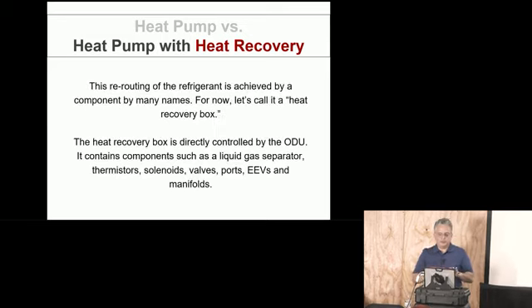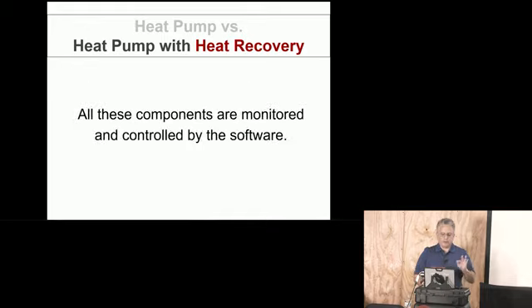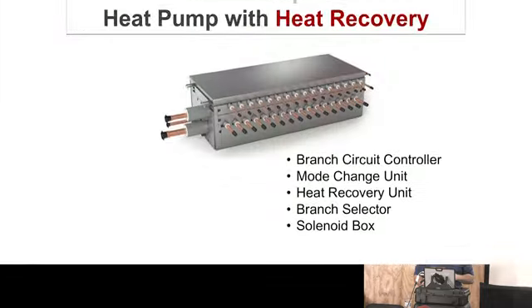This rerouting of the refrigerant is achieved by a component by many names. For now, we'll just call it heat recovery box. We'll go over the different names in a later section. The heat recovery box is directly controlled by the outdoor unit. So if you have a heat recovery box, it's an extension of the outdoor unit. It contains components such as a liquid gas separator, thermistors, solenoids, ports, EEVs, and manifolds. All these components are monitored by and controlled by the software.